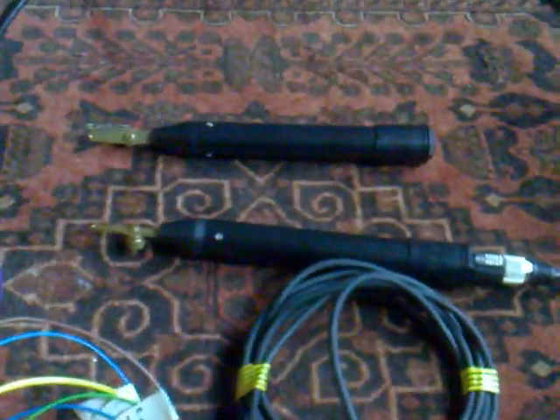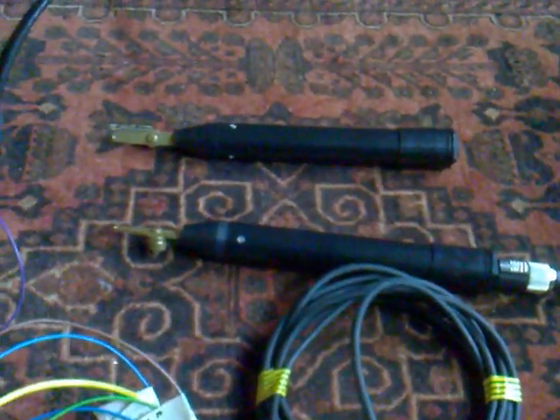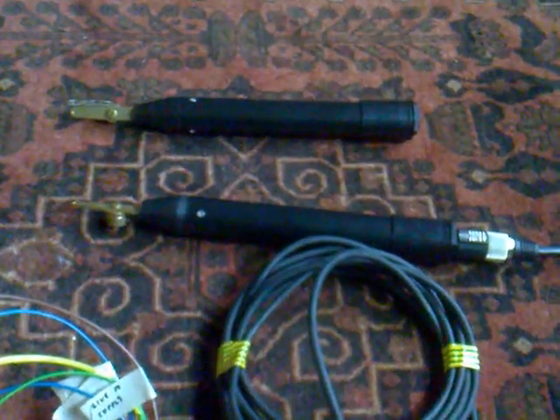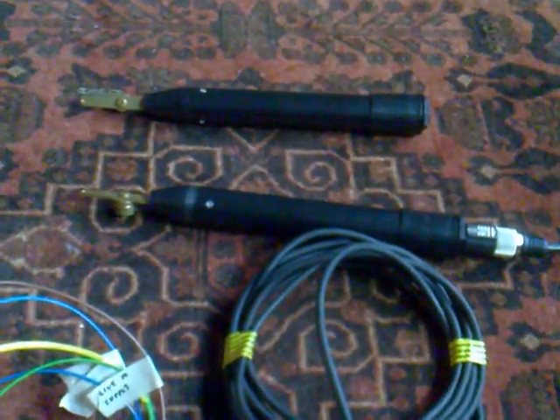And the live side of the output of the transformer would go to the switch there from your box. That will then go down a suitable 4-core flex. You can use 5-core, it's cheaper than buying 4-core. It's again 2.5mm conductor cross section, and 2 of those wires connect to the switch. So when the switch is operated here, then the solid state relay there turns on, which makes the transformer live. That turns the light on. So if I click the switch there, the light comes on, and you can be cutting away.